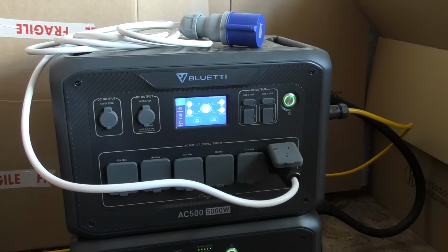Obviously the Bluetti can act in a UPS mode, so you can wire it in line with a load. The problem is that your average UK house supply is fused at typically between 60 and 100 amps, and this wouldn't be able to handle the pass-through of that current. Typical loads would be, say, 7 kilowatts for an EV charger. An electric shower could be up to 10 kilowatts. We might have an induction hob or an electric oven, and that could be 3 to 4 kilowatt loads. So one approach would be to split the load, so you have two separate distribution boards, one for the high loads and one for the stuff that you want to back up.